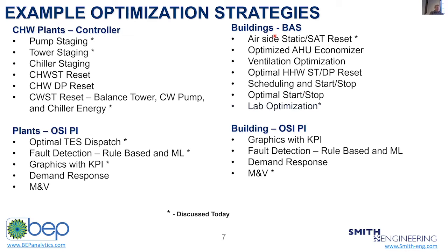On the BAS side, static reset, supply air temperature reset. This can get very complicated if you have two different fuel sources at the plant level, and then you're trying to maximize or minimize for either carbon reduction or dollar, minimizing costs. So this one can have a complex component to it, and I'll give an example of that. But optimizing economizer, that can be done within the controller very easily.